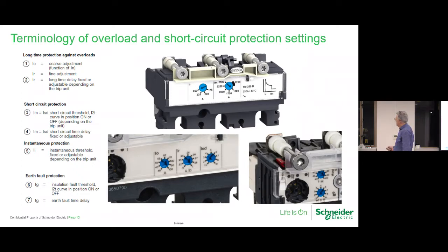So this one here is what we call a thermal magnetic trip, and there are truckloads of those out in the field, more than anything else. And obviously all sorts of brands; this is ours. This one is telling us that it will have a range of 175 to 250 amps, so this is a 250 amp thermal magnetic trip. You can see it's got four adjustments on its thermal. That's the thermal setting, and the magnetic setting is a factor of what this is set at, not 250 amps. And then there is an instantaneous value, which is not written in here, but there is one, and it will trip out. It's based upon a bimetal system with a little mechanical thing in there, and it's a very coarse type of trip. It's not what we're used to now with technology.